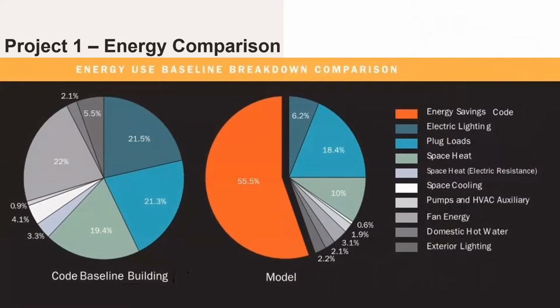Now, the colors on this chart, I did not choose - otherwise I wouldn't have done light gray, slightly lighter gray, slightly darker gray. But your fan energy was at about 3.1% in the model versus around 22% on the code baseline - a huge difference in mechanical cooling. That's because they were able to downsize the amount of cooling. This didn't have a dedicated outside air system, but it had heat recovery units - heat wheels - that would disable when natural ventilation passive cooling was in operation. So as you can see, a massive reduction in fan energy.